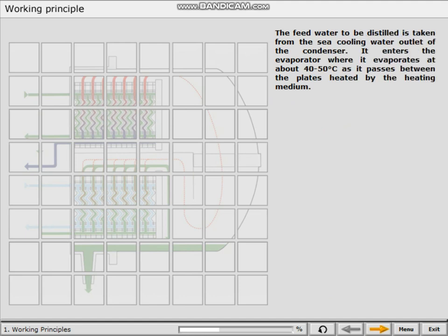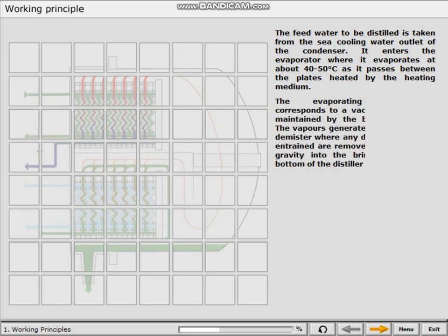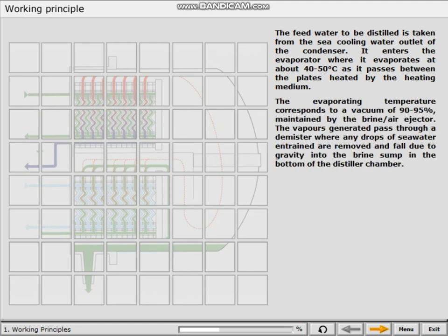The feed water to be distilled is taken from the sea cooling water outlet of the condenser. It enters the evaporator where it evaporates at about 40 to 50 degrees Celsius as it passes between the plates heated by the heating medium. The evaporating temperature corresponds to a vacuum of 90 to 95%, maintained by the brine air ejector. The vapours generated pass through a demister, where any drops of seawater entrained are removed and fall due to gravity into the brine sump in the bottom of the distiller chamber.